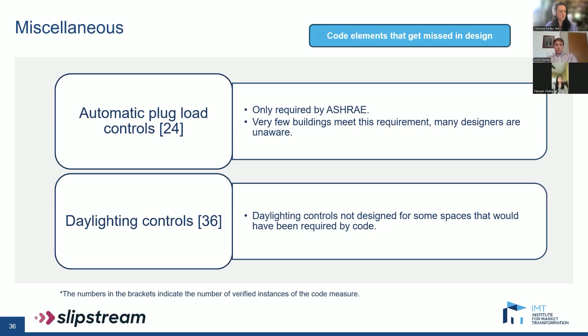And as far as lighting controls go, daylighting controls is the one place where we have seen the most non-compliance. There were instances where we saw lights adjacent to large windows that looked like they would have been required to have daylighting controls, but the lights did not appear to dim even when it was bright outside. And this seems to always be an issue that originates in the design phase and gets carried over to construction and operation.